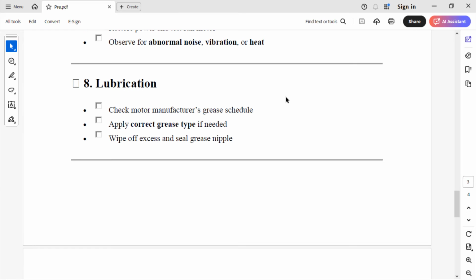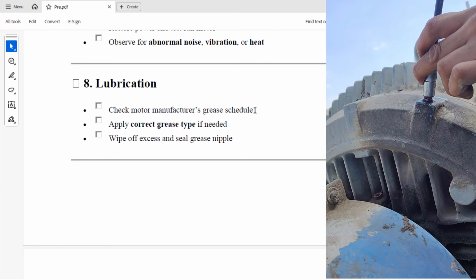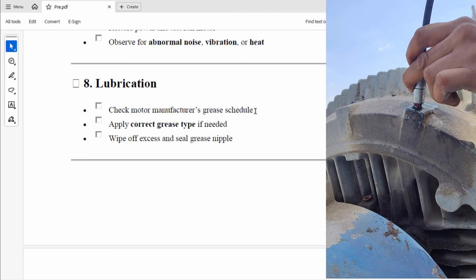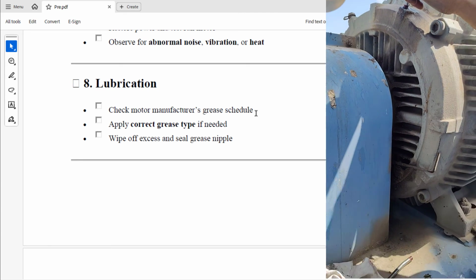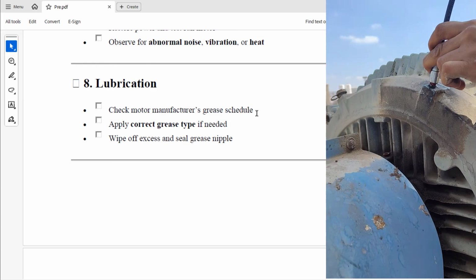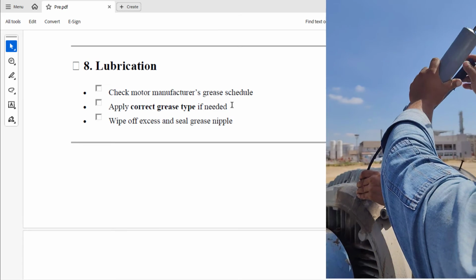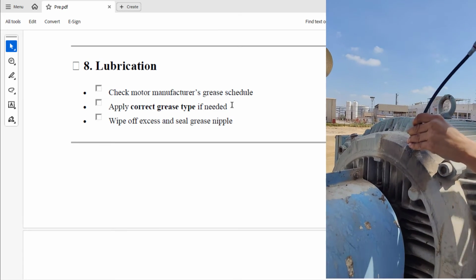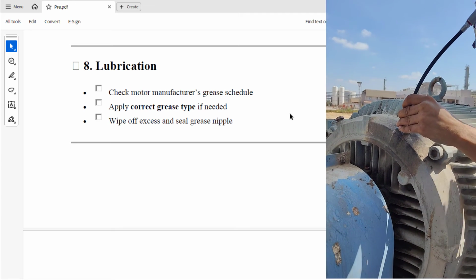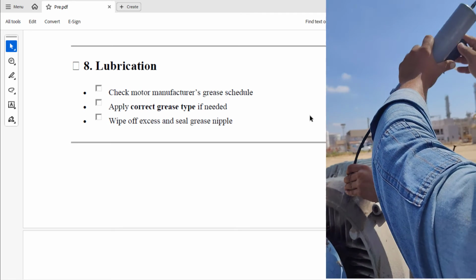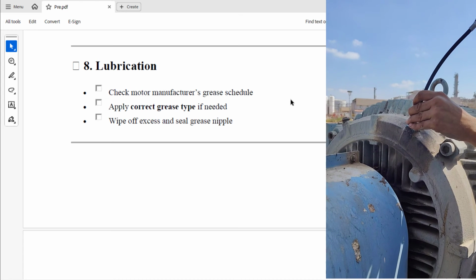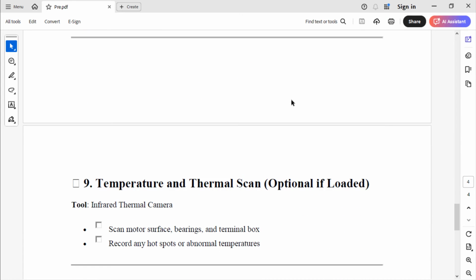Now let's check for lubrication. Check the motor manufacturer's grease schedule. If it's more than 4,000 working hours, let's apply the correct grease type if needed. Let's apply lubrication or greasing. Now, also we have to wipe off excess and seal the grease nipple.